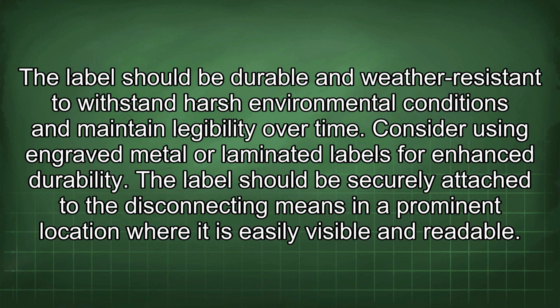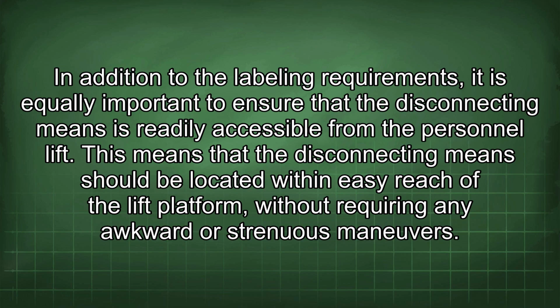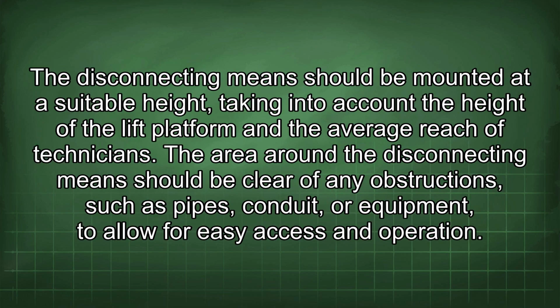The label should be securely attached to the disconnecting means in a prominent location where it is easily visible and readable. In addition to the labeling requirements, it is equally important to ensure that the disconnecting means is readily accessible from the personnel lift. This means that the disconnecting means should be located within easy reach of the lift platform without requiring any awkward or strenuous maneuvers. The disconnecting means should be mounted at a suitable height, taking into account the height of the lift platform and the average reach of technicians.